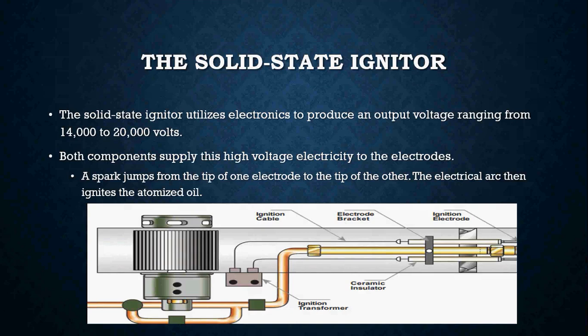The solid state igniter utilizes electronics, so it's a little bit different than your ignition transformer. It puts out an output voltage of anywhere between 14 and even 20,000 volts. I'm not 100% sure, but I do believe some solid-state igniters may put out even more than 20,000 volts. However you look at it, both of these components supply high voltage electricity to the electrodes. We need that amount of voltage sent down to the electrode tips to create an electrical arc, which in turn ignites the atomized oil.